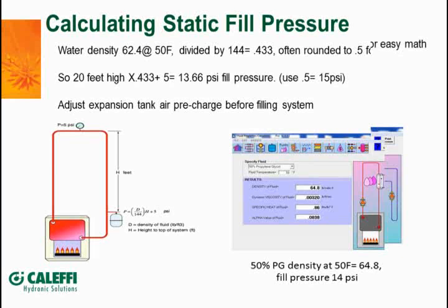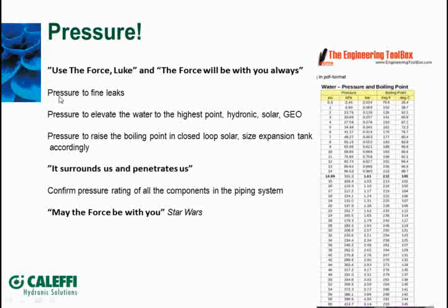So pressure, let's talk a little bit about why you want to use it. I got some little Star Wars quotes in here. A couple of things it does for you: you fill that up, you get that 5 pounds positive pressure at the top of the system. Certainly it's going to help you find the small leaks. If you've got a threaded leak or a solder joint leak somewhere, the pressure is going to help you determine where that is and find it.